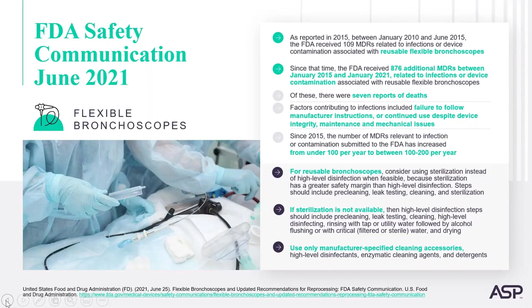Given overwhelming evidence of potential points of failure in endoscope reprocessing via traditional high-level disinfection, what can be sterilized should be sterilized. With the infection risk that endoscopes present to the patient, terminal sterilization is the preferred method of microbial inactivation and the only option in sterile environments. Terminal sterilization is recommended for flexible and semi-rigid endoscopes that enter sterile body cavities. Terminal sterilization is required for all endoscope accessories that penetrate mucosa, such as biopsy forceps and sphincterotomes.